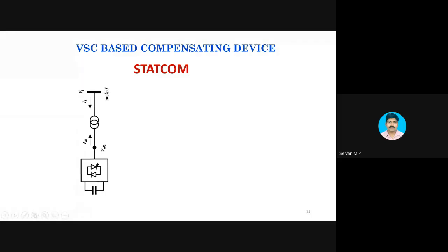If the bus voltage is higher than the VSC terminal voltage, reactive power flow will be from the grid to the VSC. Now it is going to act as an inductor. In the first case, it is going to act as a capacitor. Reactive power is flowing from VSC to the grid. If I want reactive power to flow from VSC to the grid, then this voltage should be higher. If I want to absorb reactive power, the VSC voltage should be less. So a VSC can absorb reactive power as well as supply reactive power. Or in other words, I can say it can operate in leading power factor mode or lagging power factor mode.